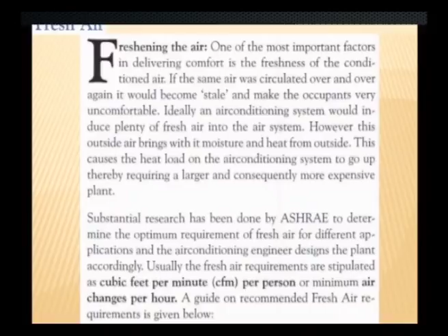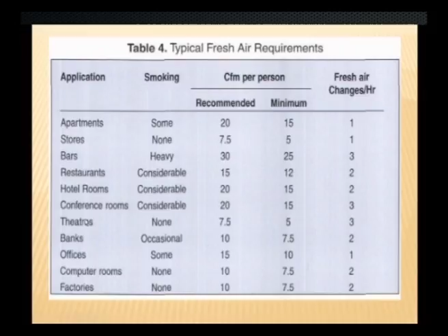The typical fresh air requirements are stipulated here. In apartments you need to give a fresh air change of 1 air change per hour. When it comes to stores also it is 1 air change per hour. The highest air change is required at bars, conference rooms and theatres. In hospitals it is necessary not only to bring in plenty of fresh air, but also to move the existing air more rapidly through the conditioned space to reduce the risk of infection.